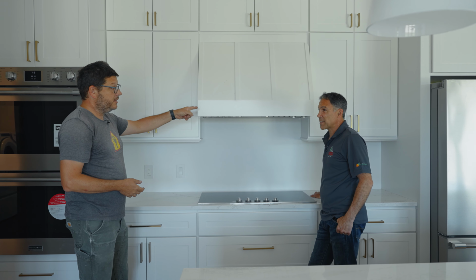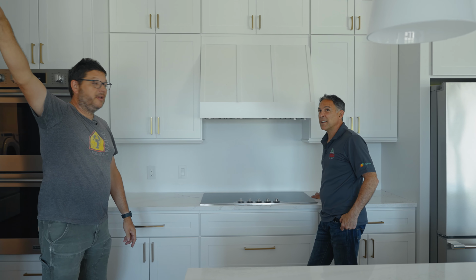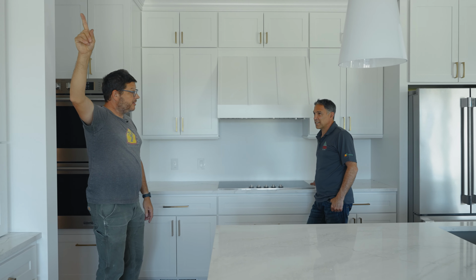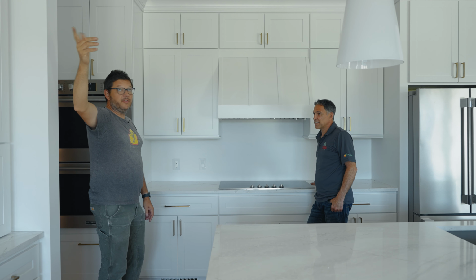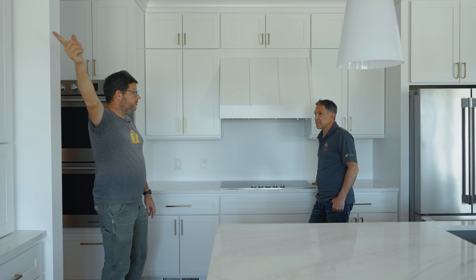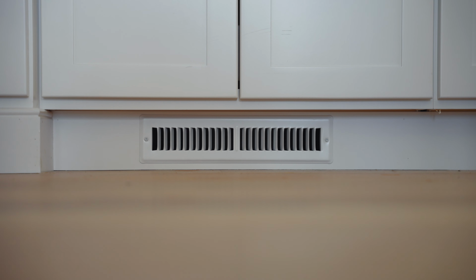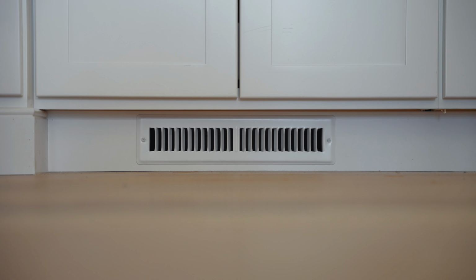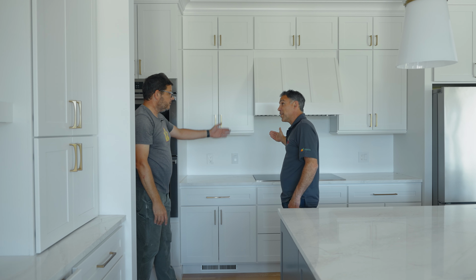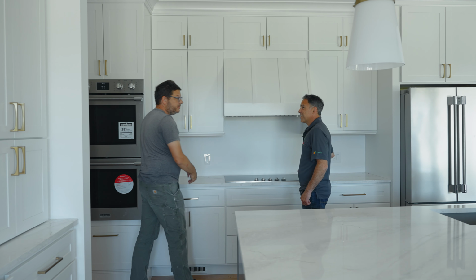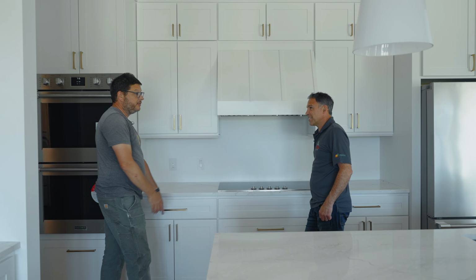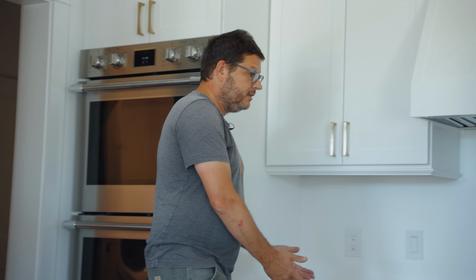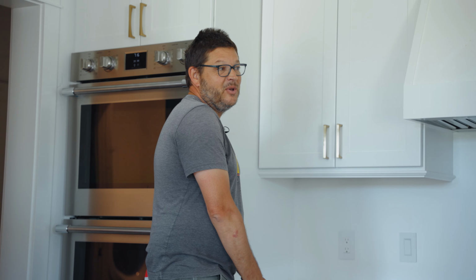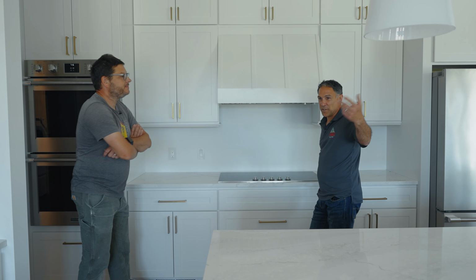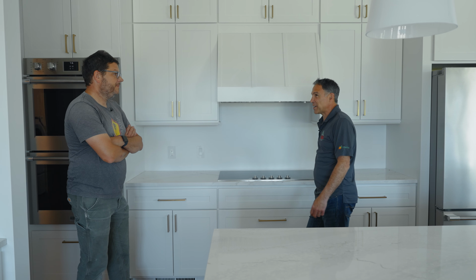Yeah, so as soon as you turn the hood on, it sends a signal to a damper that's up in the ceiling over there, in line with that pipe. It opens the damper up, and that basically creates an open 8-inch pipe that goes from outside through the ceiling, down the wall, and comes out through the toe kick right here. Right down the bottom. So as that air is going out, fresh air is going to come in somewhere. That's the path of least resistance now. Got it. It's not perfect, because if you're standing here and it's 12 degrees outside, it's going to be cold air coming in. But it's more perfect than opening up the window to try to fan on.